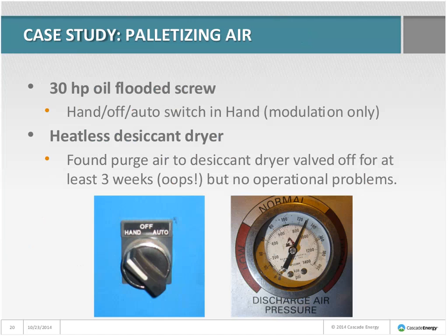Here's a smaller system with some different ideas. This is a 30-horse oil-flooded screw with a hand-off-auto switch that has always been kept in hand, as long as anyone can remember. They had a heatless desiccant dryer, and the purge air had been accidentally shut off to this dryer for at least three weeks since the last service visit — but the plant hadn't noticed any operational problems. The compressor was modulating up around almost 130 PSI.